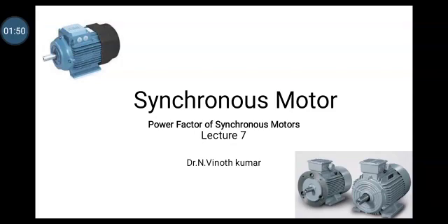But in case the rotor exciting current is less, so previous case is the same, but in this case less, that means the motor is under excited. So the deficiency in the flux can be made up by the stator. So it is not supplying the required flux, so some portion of the flux will be compensated by the stator. Now the motor draws a reactive power to provide the remaining flux. So in this case the motor will operate at the lagging power factor.